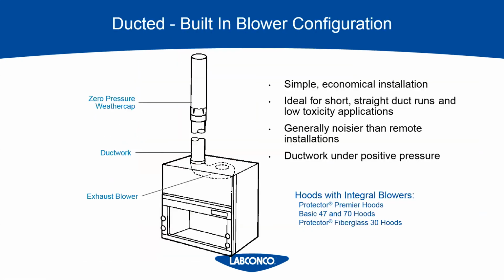Because now we're going to look at the built-in blower configuration, where the blower is sitting right on top of the fume hood and it's actually pushing the air up. So going back to the previous one, this one's pushing the air up, the other was pulling the air from the exhaust fan location on the rooftop. So that's the difference. This duct run can go directly vertical, but on this version, you can't size the blower. The blower is built into the top of the hood, so you need to make sure your duct run is appropriate for that blower's fan curve.